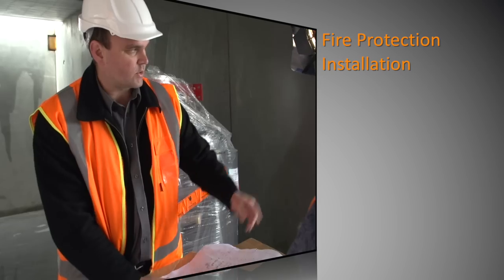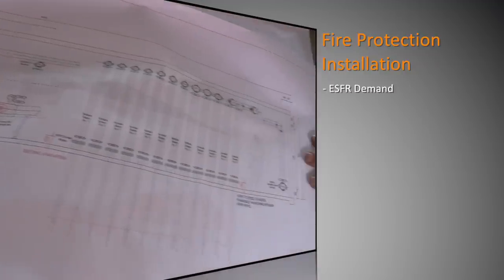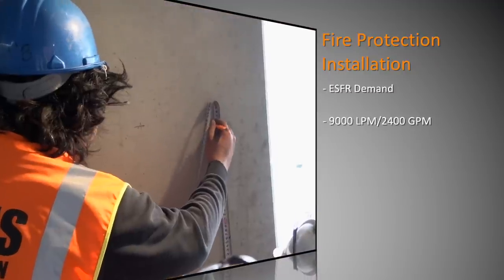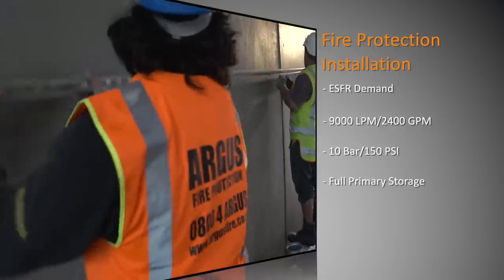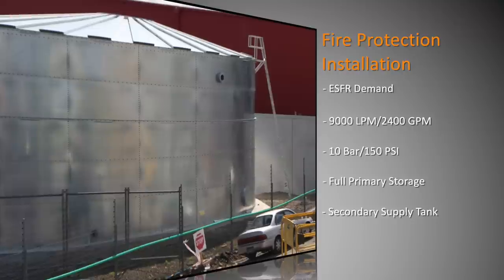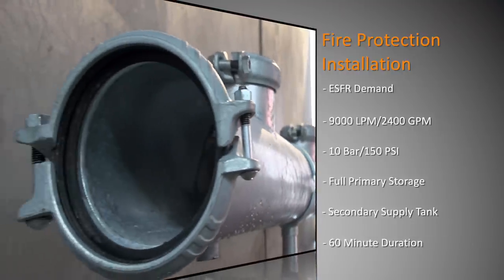The overall objective of the system we're installing is a ESFR demand of about 9,000 litres per minute at about 10 bar of pressure. We've got a full stored capacity for our primary supply and a secondary supply which is a tank with a town main infill to achieve a 60 minute duration of water supplies.